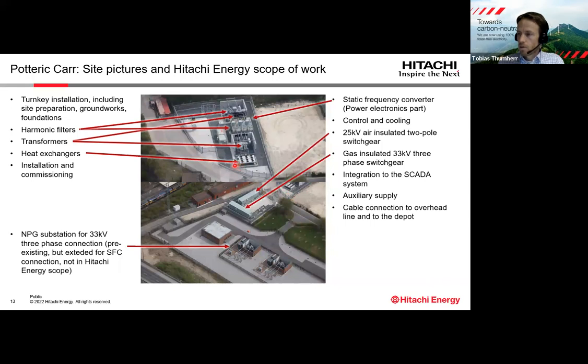And also on this slide is shown what is included in the scope of supply of Hitachi Energy for this project. So it's a turnkey installation, including site preparation, groundworks, and foundations. We have the static frequency converter with the power electronics that is here included in a container that is a little bit hidden between the filters and the bus bars, and then the control and cooling container here. There are harmonic filters on top here and the transformers on both sides.